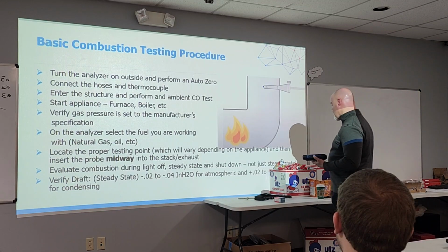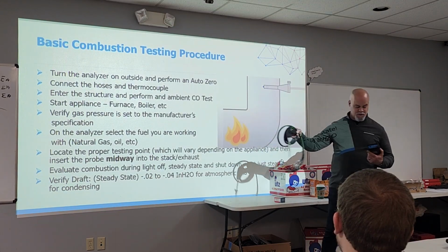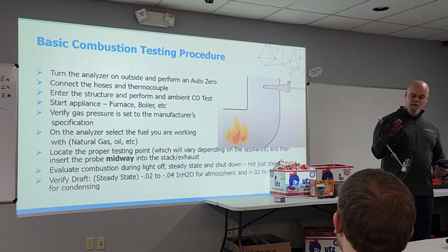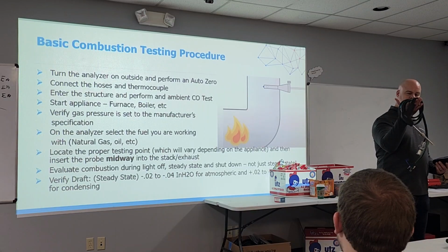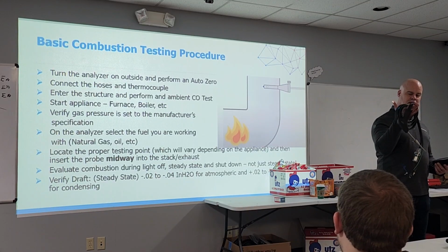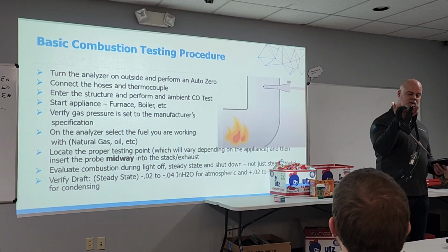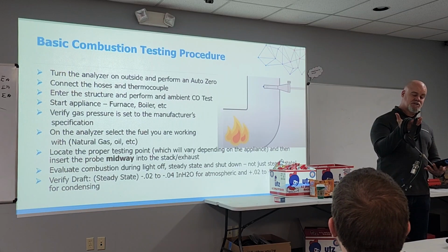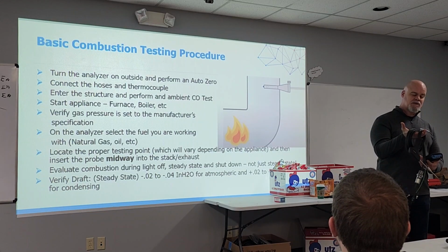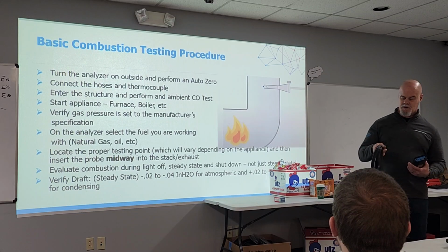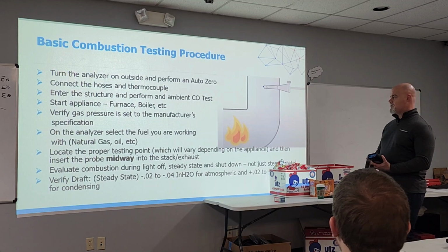The reason I don't want any probe or hose attached when I start this up is that I don't want you to run the risk of pulling in the remnants of a previous combustion test sitting dormant in the probe and hose assembly. When you turn it on, it establishes a suction and pulls those contaminants in, which sullies that starter protocol. I don't want you to do that, okay?